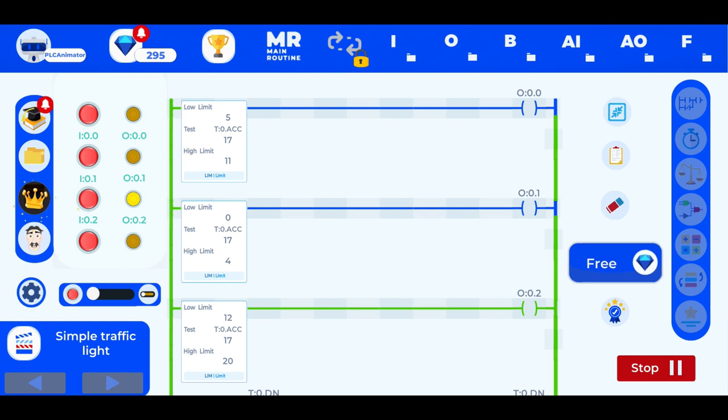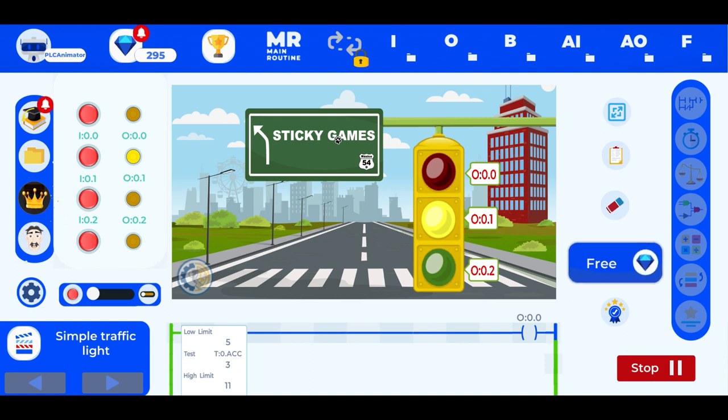Now, the advantage here with limits is if we first indicate a seconds range, it's only going to listen to this range for the one that we have for output. And whenever it's out of range, it's not going to listen to the rest of the outputs because it's not the corresponding angle for it to power on. So in theory, we're decreasing the lines. So we're only using 4, and now we're only using one timer only. So here we need to analyze correctly our limits as far as seconds or ranges, whatever you need. Test it, try it, and obviously this method is going to be good for the rest of our PLCs and our brands.